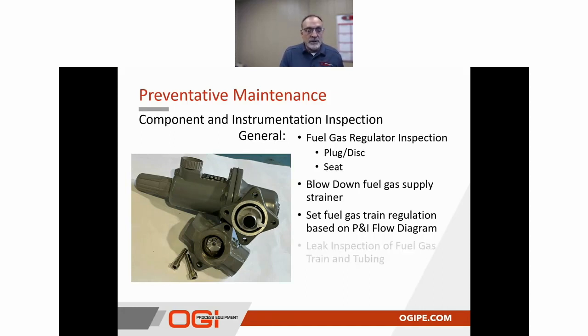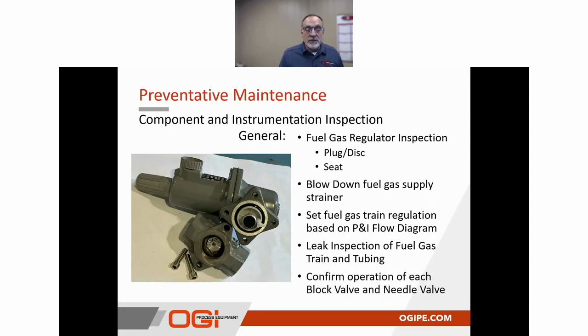And then, of course, with taking everything apart, we want to confirm, from a leak inspection standpoint, that all the piping and tubing in that gas train are free of any potential leaks. In doing so, we also want to confirm the operation of block valves and needle valves, and do a soak test on all the packing glands to ensure that we don't have any leaks in those cases. If there are any leaks or repair required, then we'll conduct as much as we can. Or in some cases, somebody may have a kit that would repair that potential damage.